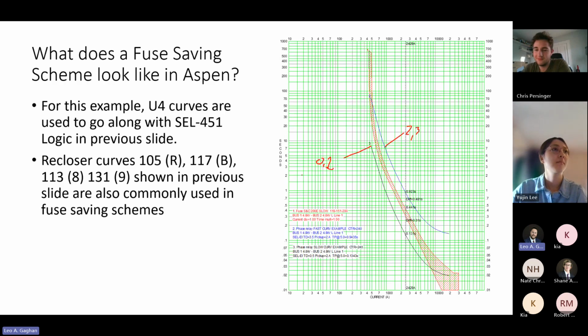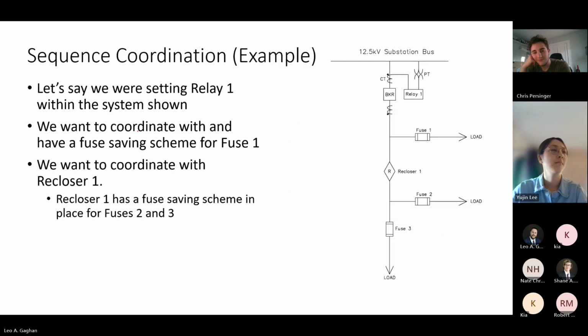So yeah, like I said, there's the logic for it. 2 different overcurrent elements, one supervised by shot 0 and shot 1, and then the second one is always just active. It kind of gets masked by the first one. So once the first one goes away, the second one, we just have that set to a 1, and it would only operate for higher order shots. So yeah, I guess that's fuse saving.